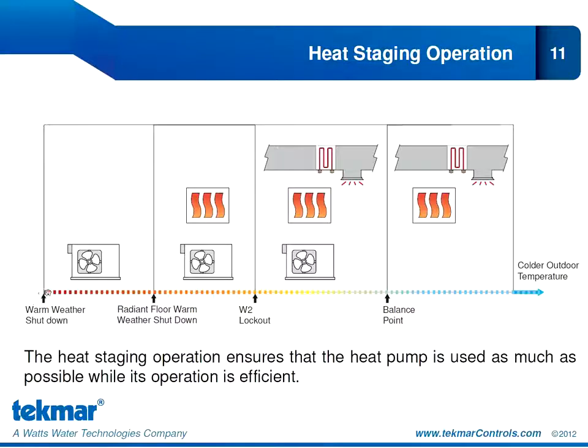As the outdoor temperature drops below the warm weather shutdown, we may bring on stage 1 and stage 2 of our heat pump. If the outdoor temperature continues to drop, we see a new setting called radiant floor warm weather shutdown, and we will discuss this in greater detail later in the webinar. What this setting does is it holds off the radiant slab until the outdoor temperature is sufficiently cold enough that we're confident we're not going to experience any heat-cool switchover that's associated with the milder shoulder seasons. So it is now safe to bring on our radiant floor as first stage heat and our heat pump as the second and third stage of heat.